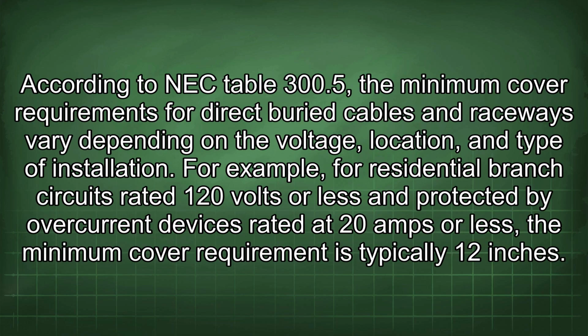According to NEC Table 300.5, the minimum cover requirements for direct buried cables and raceways vary depending on the voltage, location, and type of installation. For example, for residential branch circuits rated 120 volts or less and protected by overcurrent devices rated at 20 amps or less, the minimum cover requirement is typically 12 inches.